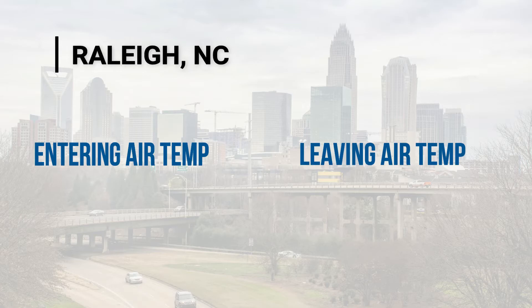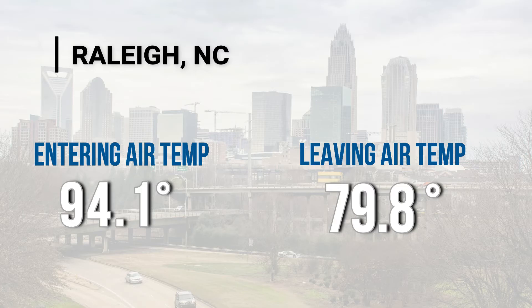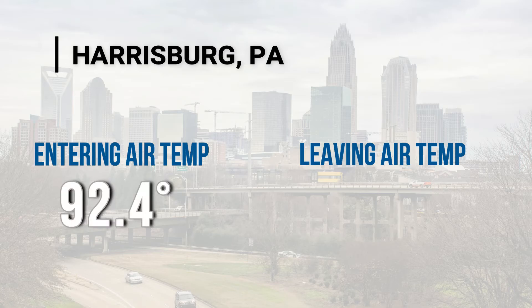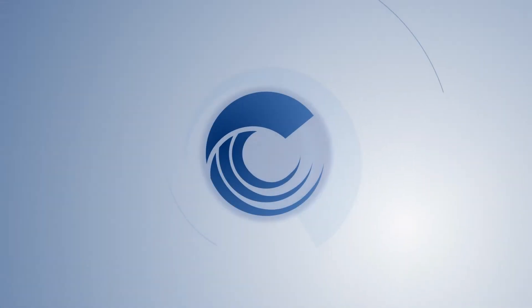In Raleigh, North Carolina, we would have an entering air dry bulb temperature of 94.1 and a leaving air temperature dry bulb of 79.8, achieving about a temperature drop of a little over 14 degrees. In Harrisburg, Pennsylvania, you have a 92.4 entering air temperature dry bulb and a leaving air temperature dry bulb of 77.8, or just a little over a 14 degree temperature drop. It's not for everything, but you should consider it when you're trying to cool a space by 15 degrees or less.